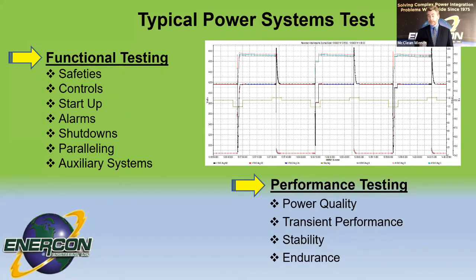It's good to do that as soon as you can, in case you do have an issue with the way that the generator is wound. You're not going to end up wasting a lot of fuel and a lot of testing if you end up having to pull that generator and send it back to the manufacturer to be rewound. So the next part would be transient performance. This is adding and dropping loads quickly. That's the graph in front of us, characteristic of a transient.